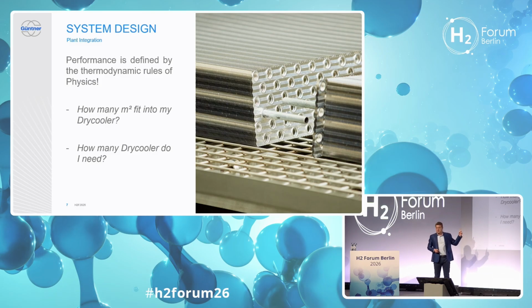In the large V-types I showed earlier, you can pack up to 3 megawatts, depending on the temperatures used. Nowadays industry standard says you can only pack maybe 1.5 to 1.8 megawatts into one of the large V-type coolers. So if you need 22 megawatts, you can do the math — it's about 21 to 25 units of a large dry cooler that you need.